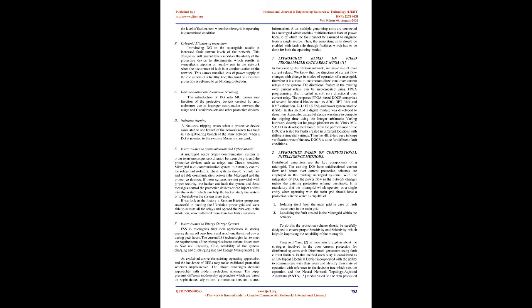If these systems are not provided with proper security, a hacker can hack the system and send messages to control the protective devices, or can inject a virus into the system which can help the hacker study the system or break down the system in no time. If we look at history, a Russian hacker group was successful in hacking the Ukrainian power grid and was able to actuate all the relays and open the breakers in the substation, which affected more than 2 lakh customers.